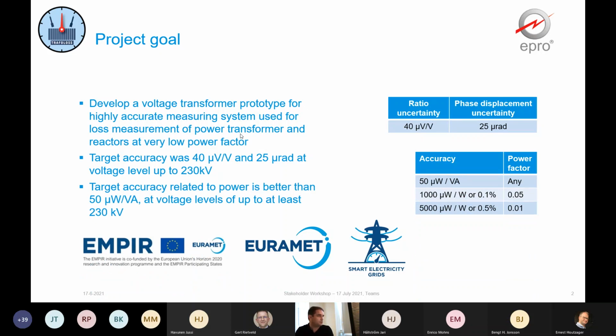The target accuracy of the project related to the power, as you can see, is 50 microwatt per VA, and when we show this for a different power factor, let's say 0.05 here in the table, then it becomes 1000 microwatt per watt, or 0.1%. Similarly, for the power factor 0.01, it is 0.5%. So that was the primary project target in the sense of accuracy.